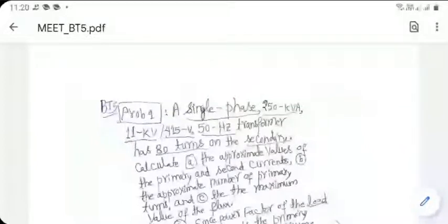kVA rating is given. Recommended primary voltage is always on the left side. Then an oblique sign comes in generally, and the secondary voltage is mentioned. The voltage on the left side is always the primary voltage. That is the way nameplates are printed. Voltage on the right side of the oblique sign is the secondary voltage. All voltages are RMS values. Frequency of operation is also printed generally on the nameplate. Number of turns may not be printed, but the info is available for a given transformer.